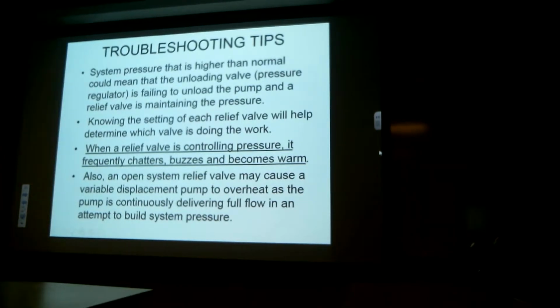If that goes on for a long period of time, what you might expect is that the hydraulic fluid will turn black. The hydraulic fluid begins to receive excessive heat, and it will begin to char the fluid so that it discolors and becomes really black. But it takes quite a bit of time for that to happen. Initially, what you might notice is that the relief valve is just chattering and buzzing.